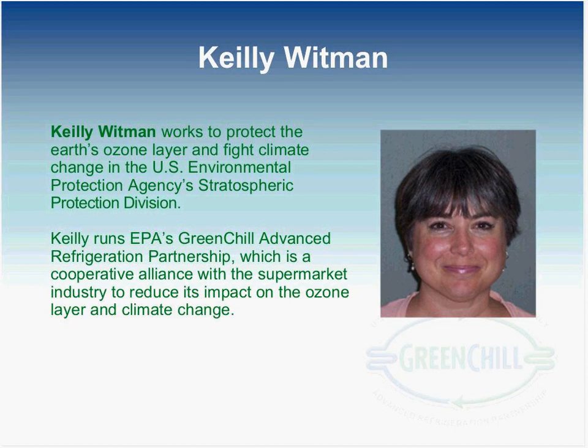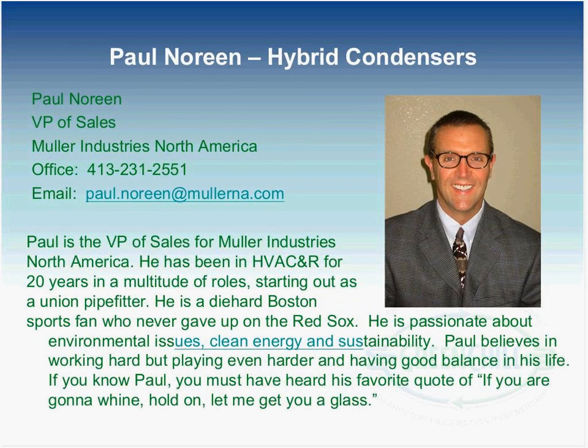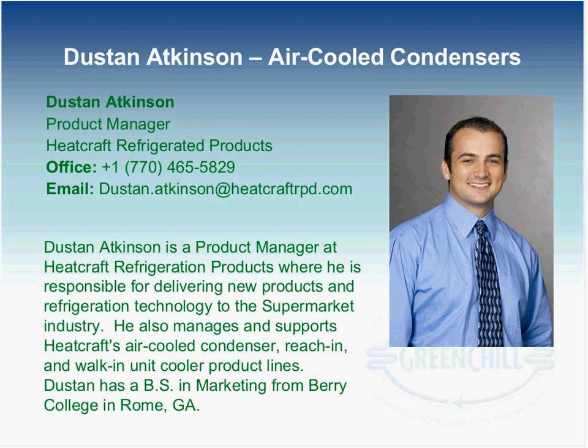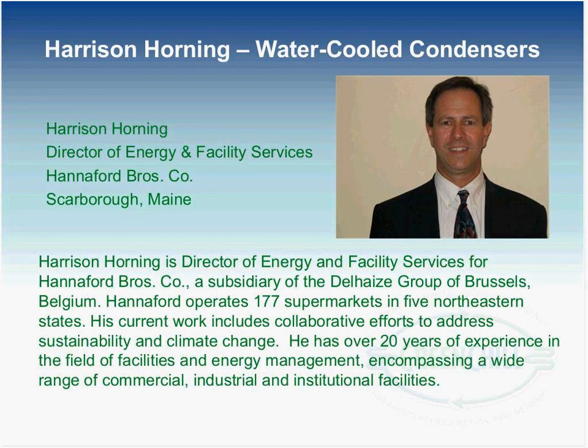I think Paul did mention that it's kind of unique, and they do have the data to support it, that when the water does turn on, the pressure drop across the pad is actually reduced because the water fills the pores of the pad, and the static pressure actually reduces when the water's running. That was my first concern, that when the water was running you'd have a much higher static pressure. I think the technology of the motors they're using is a pretty incredible smart motor. The impact of the static is much smaller than it would have been on old motor technology. They can get you the details, but I don't think it's significant enough to be a concern.